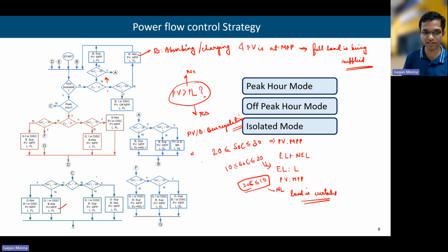But if SOC is less than 60%, we need to maintain some charge in the storage so that it can be used in peak hours. We are talking here about the off-peak hours. This is the off-peak hour. C is for off-peak hours. We want to have sufficient energy stored for peak hours. Therefore, if the storage SOC is less than 60%, what are we going to do? PV will be acting at MPPT, and it will charge the storage.